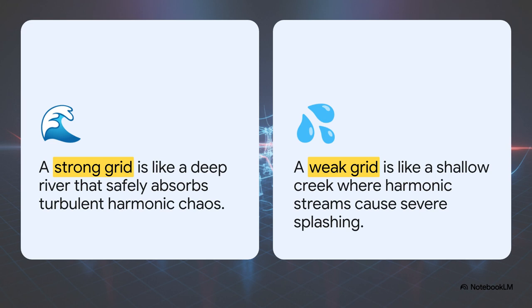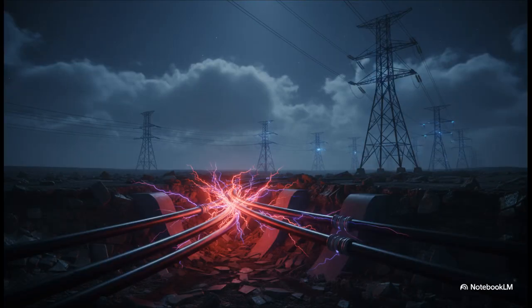But a weak grid, one with a low fault level, that's like a shallow creek. Dump that exact same turbulent stream into the creek, and the water violently splashes everywhere, flooding the banks. In our grid, that splashing is severe harmonic voltage distortion, which can overheat transformers and literally destroy equipment. The really tricky part we face today is that our modern infrastructure choices are inadvertently turning our deep rivers into shallow creeks.